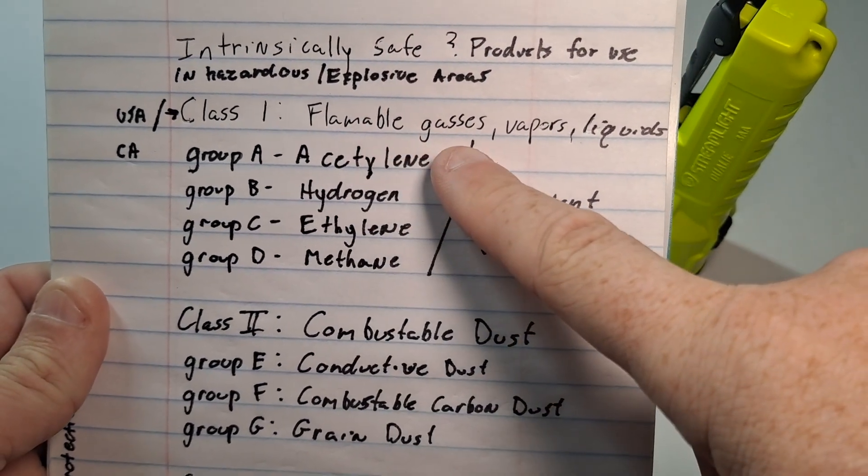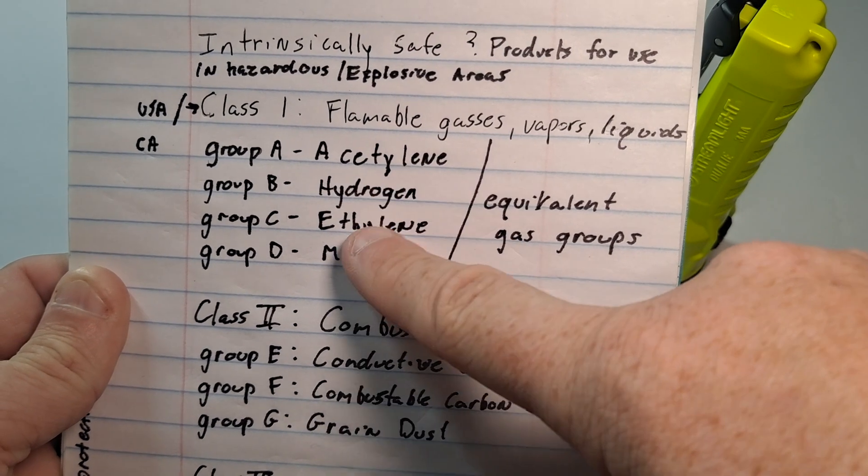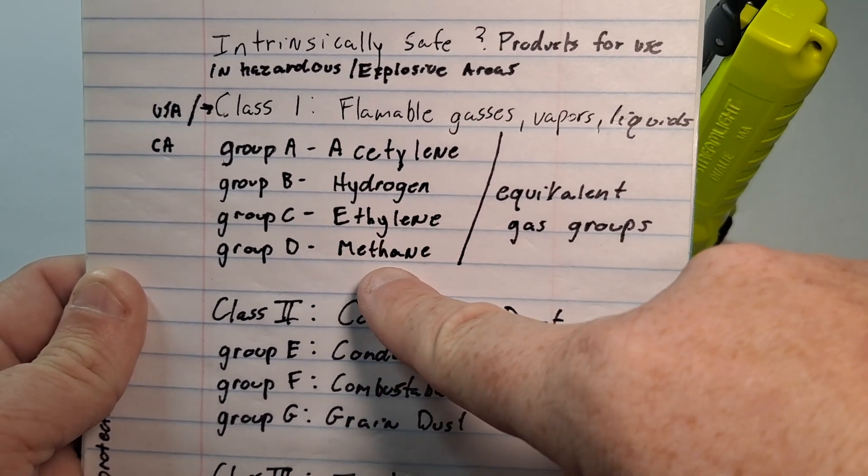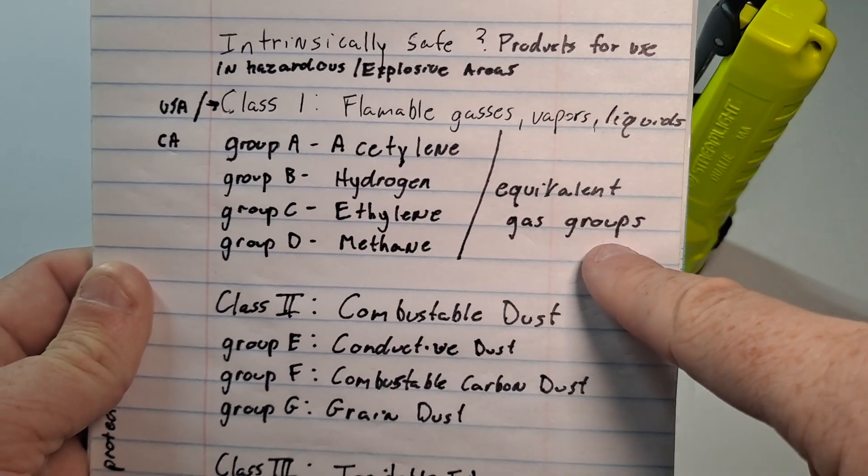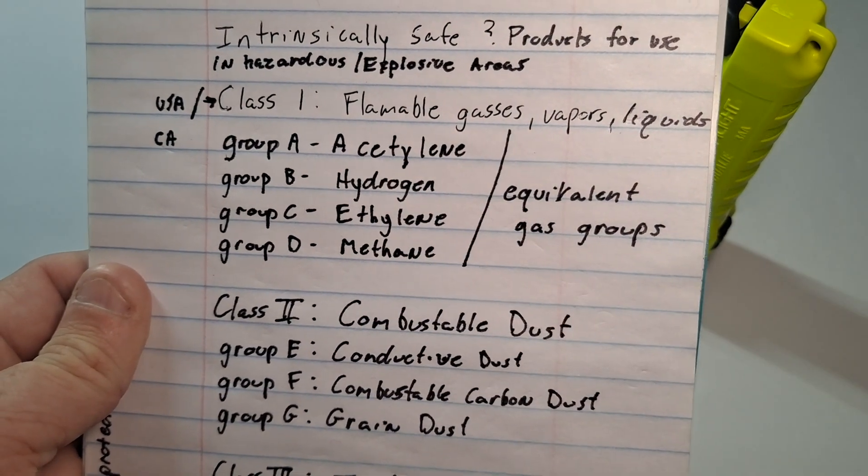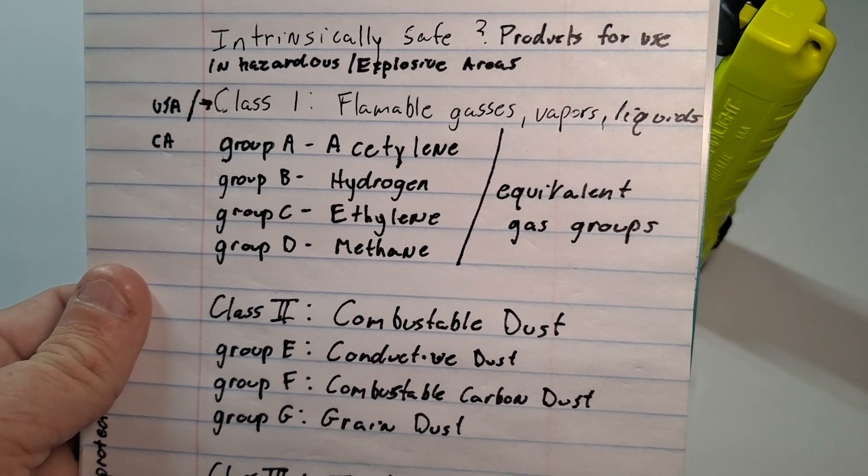Class one is flammable gases vapors and liquids. Group A is acetylene. Group B is hydrogen. Group C is ethylene and group D is methane. And for each of those groups an equivalent gas group. So whatever else is in the acetylene the hydrogens the ethylene anything that has those products in it could be a flammable gas vapor or liquid.